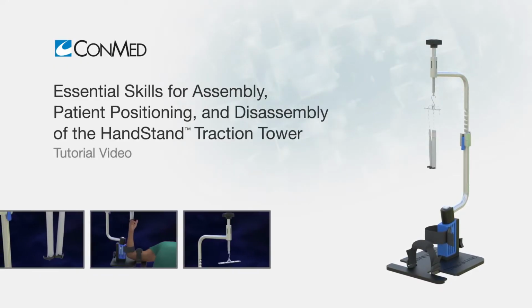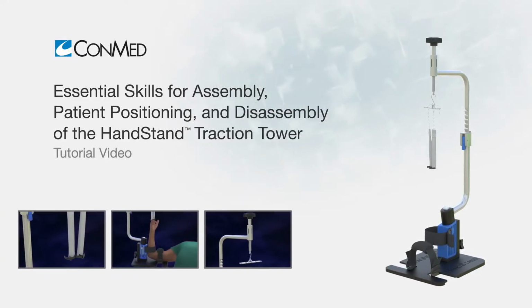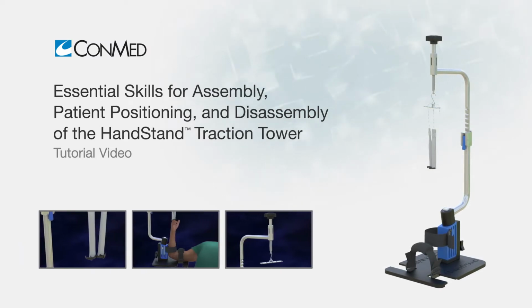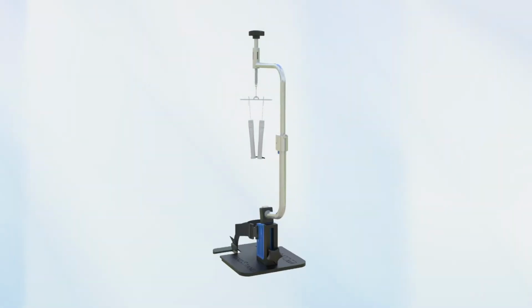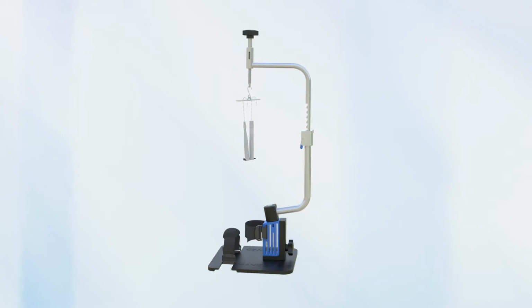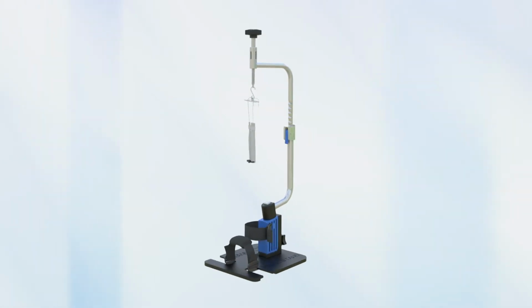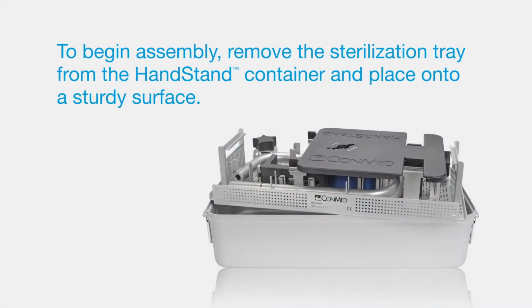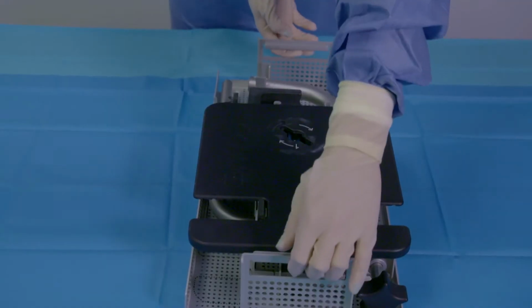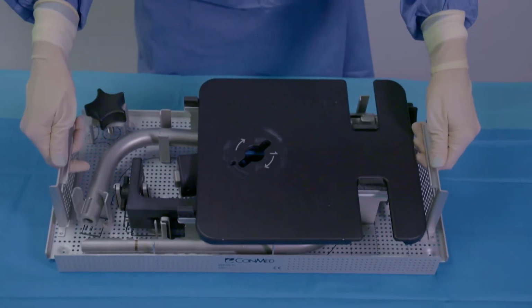The handstand traction tower is designed to be used in conjunction with either an armboard or hand table. Prior to positioning the patient, all pads must be removed from the armboard or hand table. To begin assembly, remove the sterilization tray from the handstand container and place it onto a sturdy surface. The tray contains the handstand components.